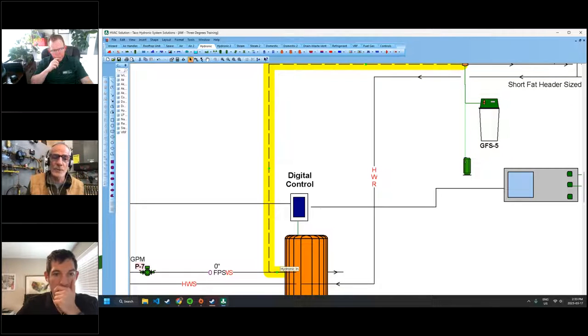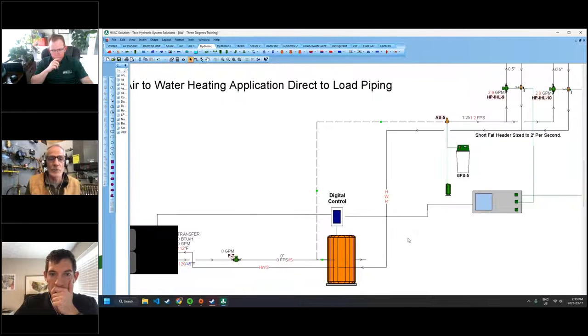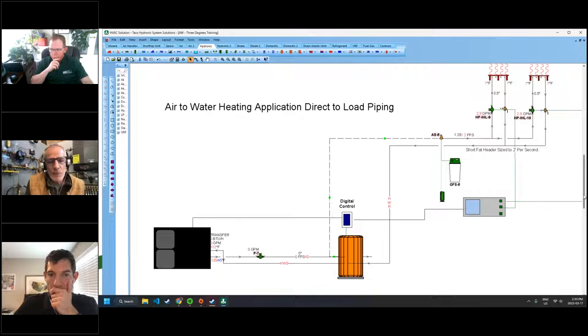So if you've got a load that's coming on and the heat pump's running, there's no reason to go through the buffer tank if it can take all that output of the heat pump. So that's what direct to load is. So when we looked at that, we said, well, if a 4 pipe is good for certain conditions and the 2 pipe can do this, if you add the two together and average it, you come up with a 3 pipe. And what a 3 pipe does differently than a 2 or 4 is you go direct to load on the top, but on the bottom, you also have the coldest possible return going directly to the heat pump.